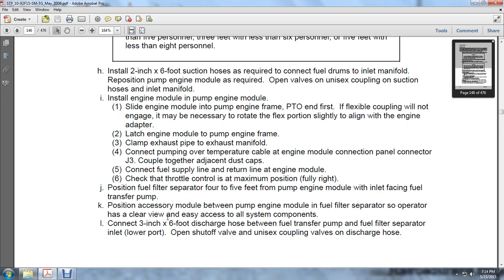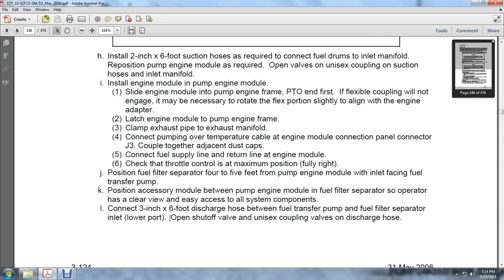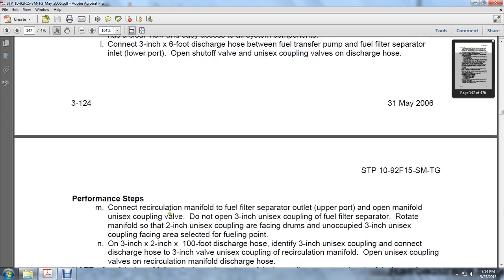Connect the 3-inch, 6-foot discharge hose between the fuel transfer pump and the fuel filter separator. Open the shutoff valve and unisex coupling on the discharge hose, the lower port. Connect the recirculation manifold to the fuel filter separator outlet port, the upper port. Open the manifold unisex coupling valve. Do not open the 3-inch unisex coupling on the fuel filter separator.